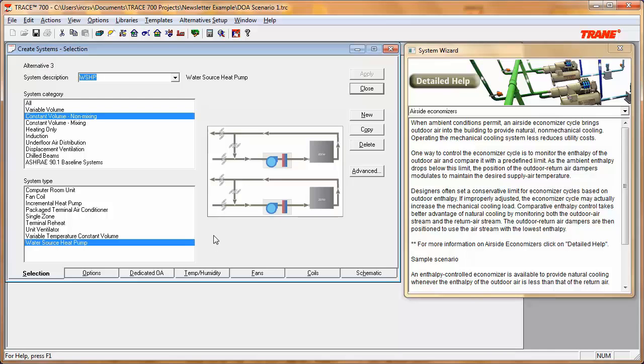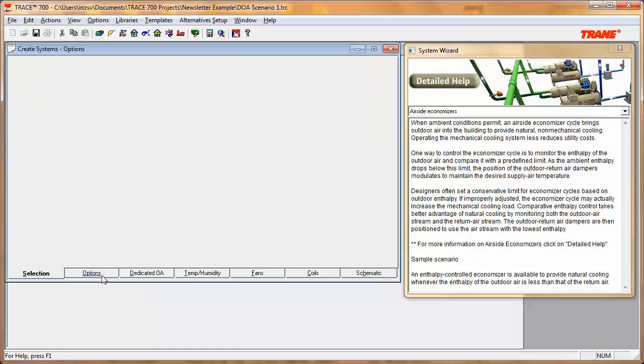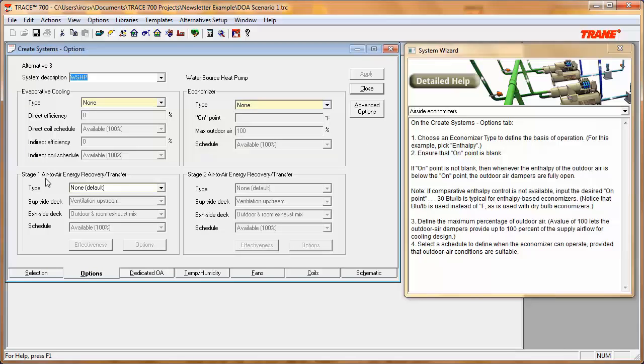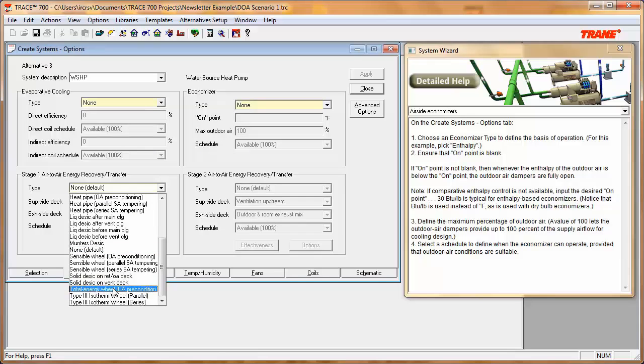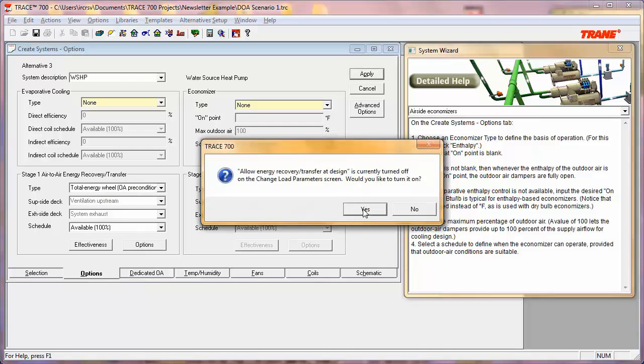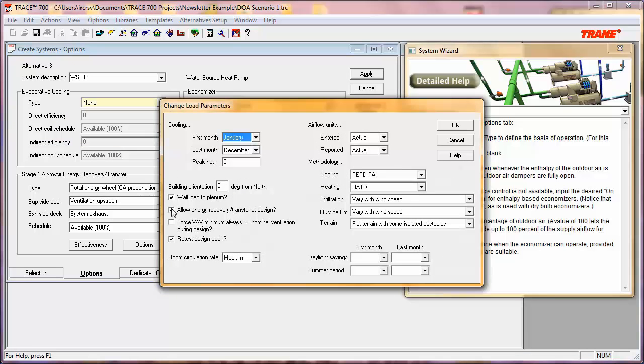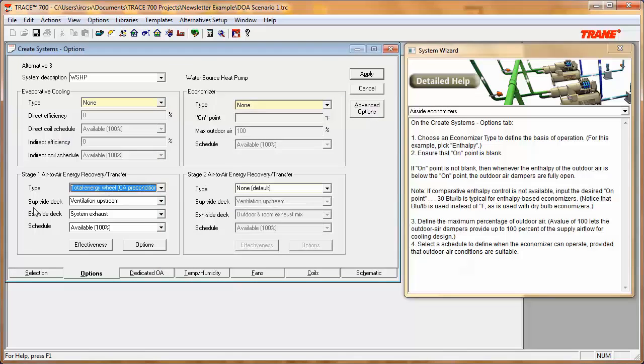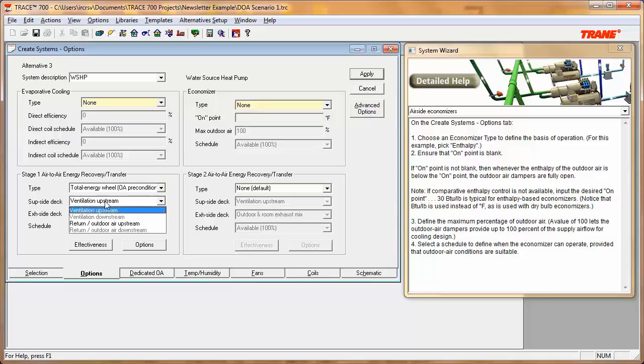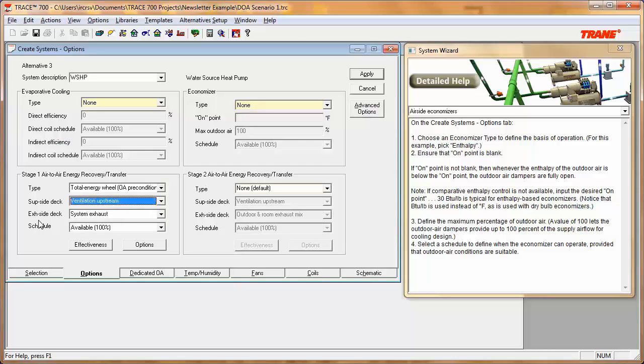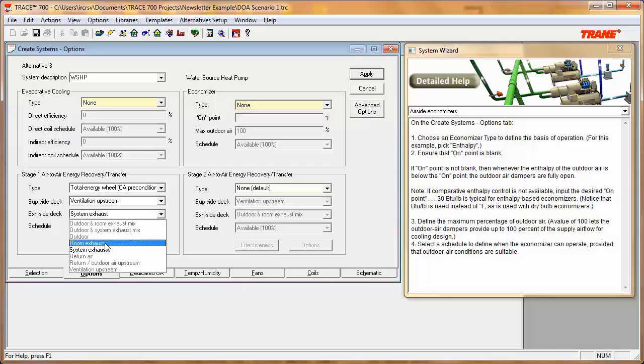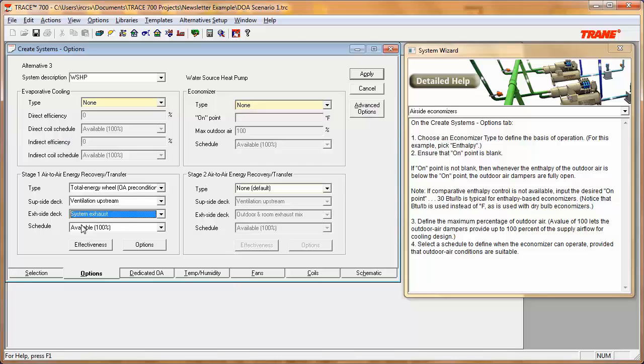To model a total energy wheel upstream of the dedicated outdoor air coils, go into the Options tab. Under Stage One Air-to-Air Energy Recovery, select total energy wheel OA preconditioner. A message will appear asking if you want to account for energy recovery during the design calculation — select yes. You can change that later by going to Actions, then Change Load Parameters, and deselecting that box. For the supply side deck, you have the option of placing the wheel before the ventilation coils or before the main coils — I'll select ventilation upstream. For the exhaust side deck, you can choose system exhaust, or if you have room exhaust air flows defined in your rooms' air flows tab, you can select room exhaust. Always make sure to select the correct air flows.